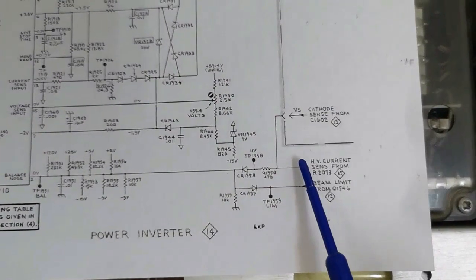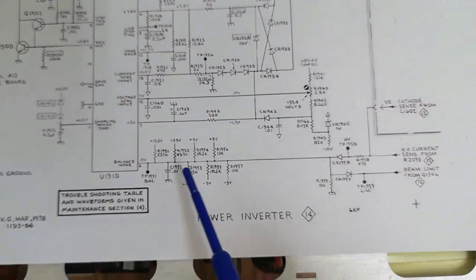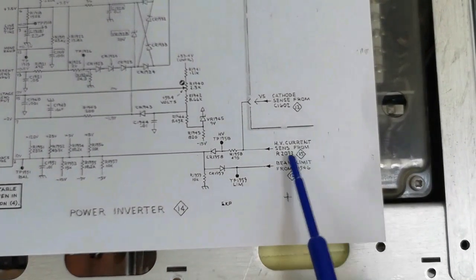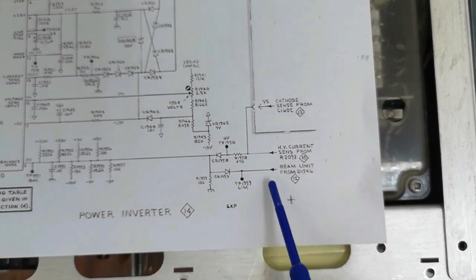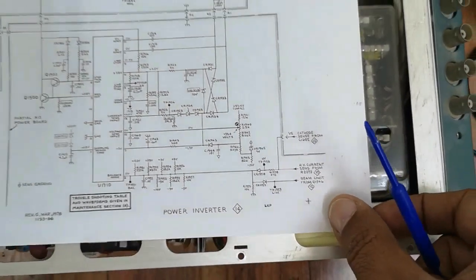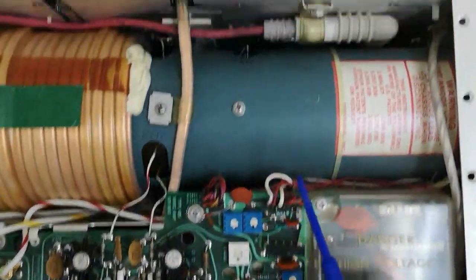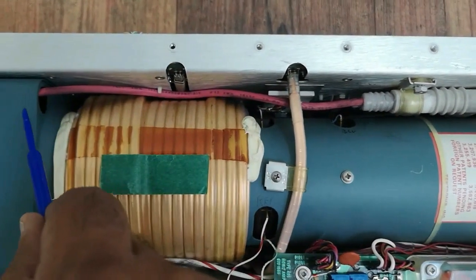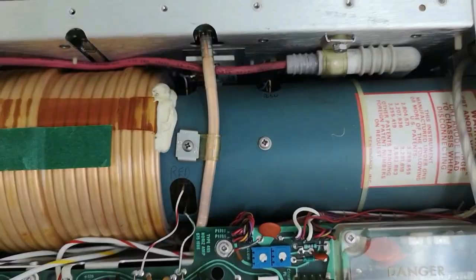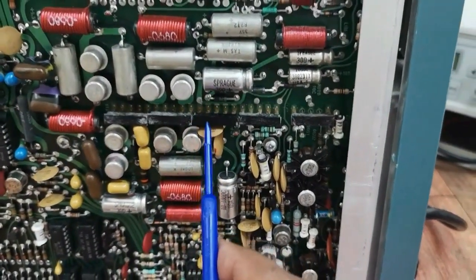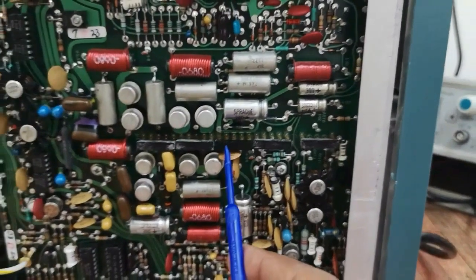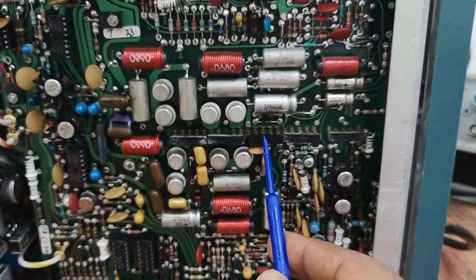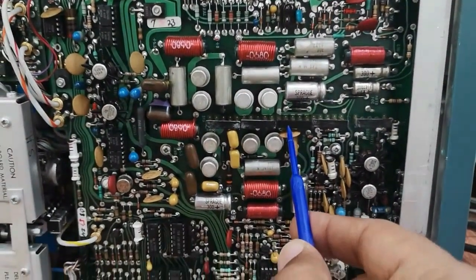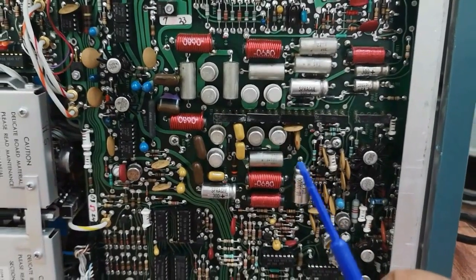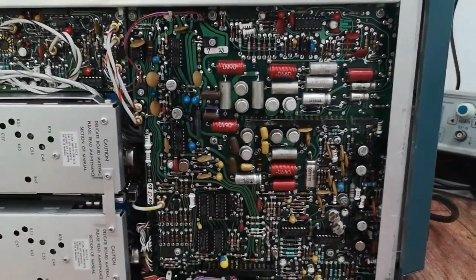We have here also other protection parameters activating the same input: the high voltage over current plus high beam current as well. In fact, I already disconnected this high voltage tube cable, and there is a procedure provided in the manual to disconnect and bend pin 3 at the comb U connector, which will isolate the high current at the high voltage section. This was all performed, but no change was observed.